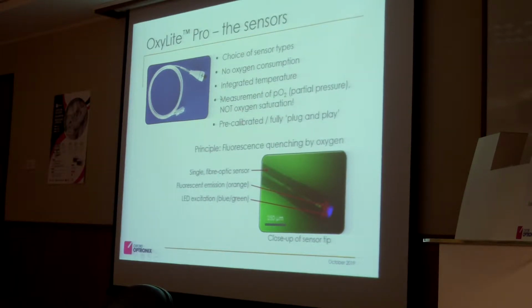We do offer those sensors with temperature because the partial oxygen pressure needs a temperature value to correct for the temperature, so to speak. Yeah? So you can have just an oxygen sensor and the instrument will receive a manual input from you telling it: I have a controlled experiment, my animal is always 37 degrees, I have it on a heating pad. So you can use 37 degrees, but if your animal has fever, heat stroke, shock, the temperature might go up or down. You might want to measure oxygen and temperature at the same time. That's why we also have sensors with temperature.